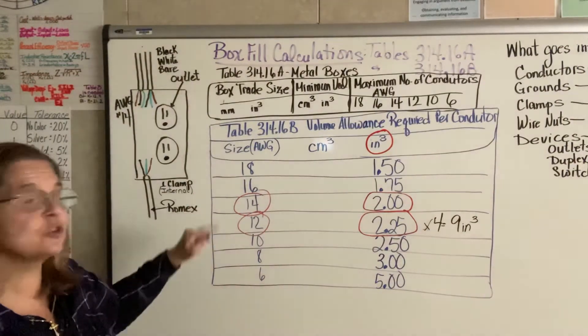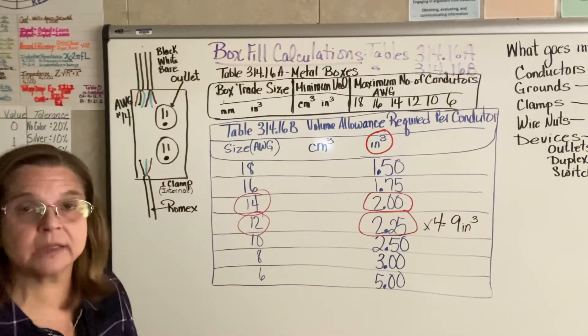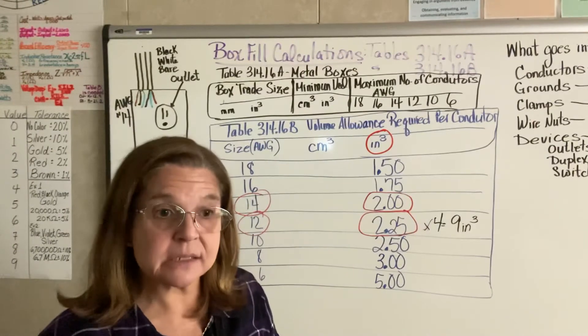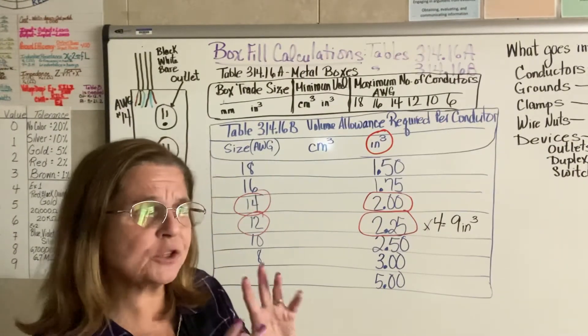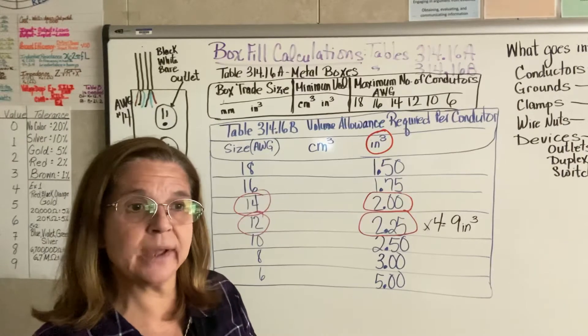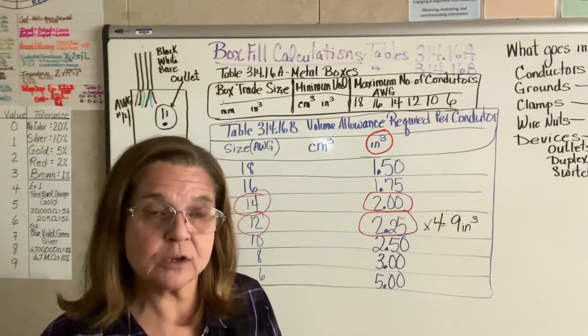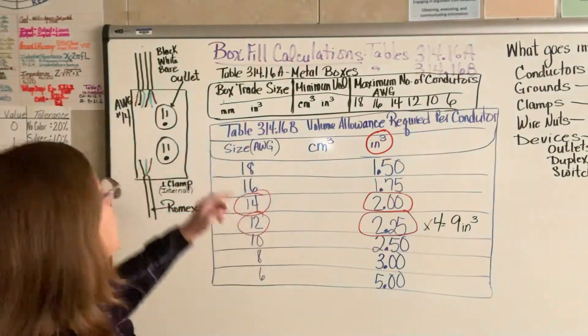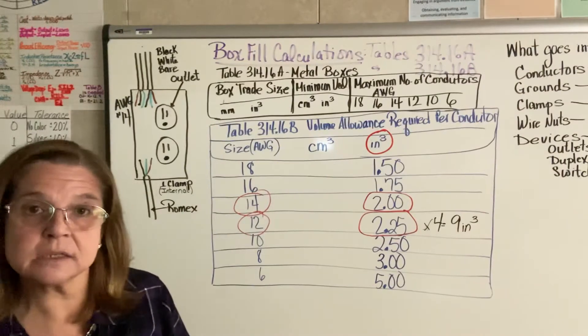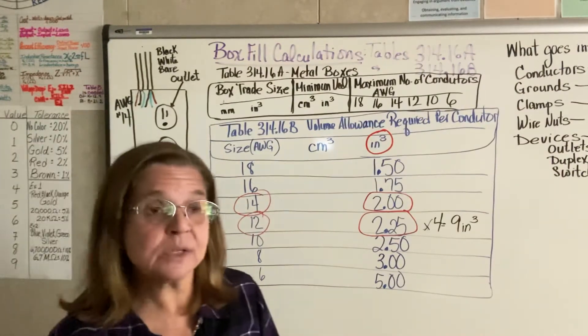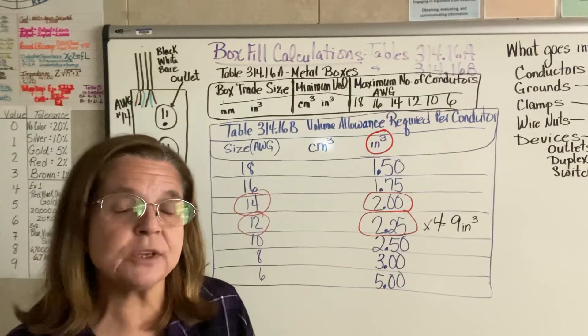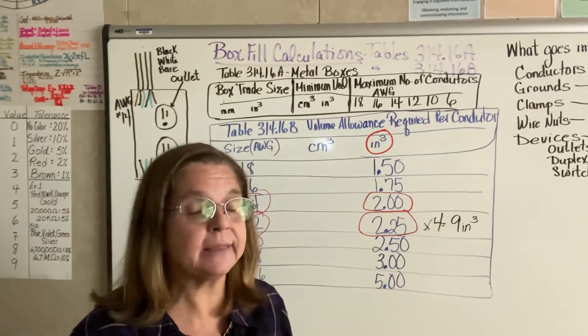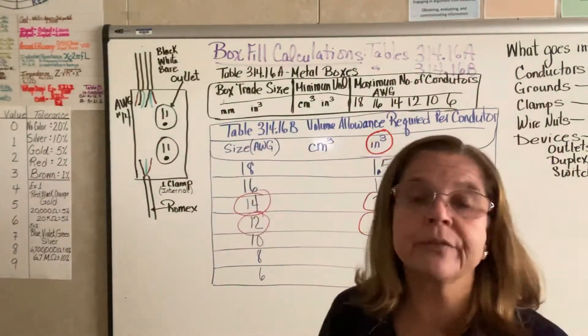And now I need to know what size box can I use to put everything inside where the wires are not overcrowded. Because if they're overcrowded, we can end up causing damage to the coverings on the conductors. And if it's too tight, we can cause overheating. So we need to be sure that our calculations make sense, that they work, and they fit the NEC code.